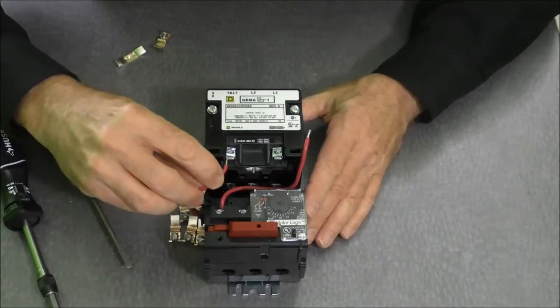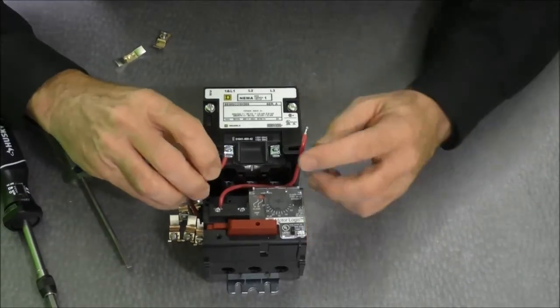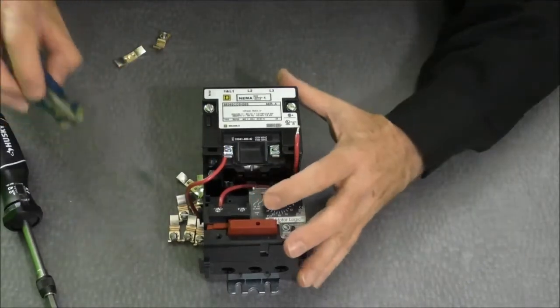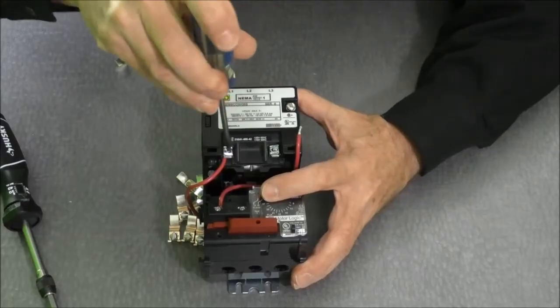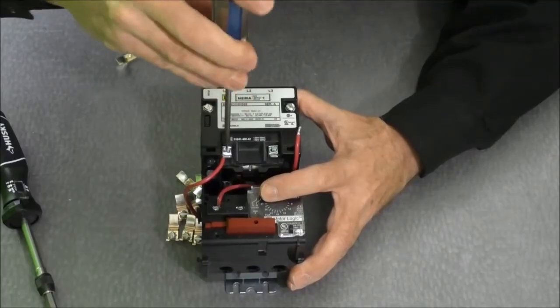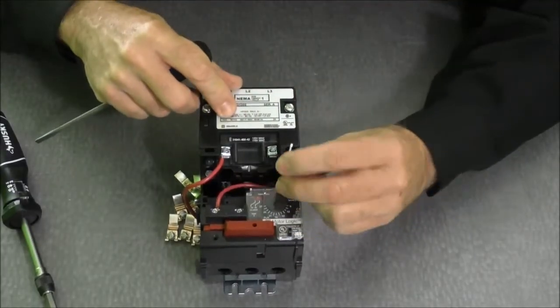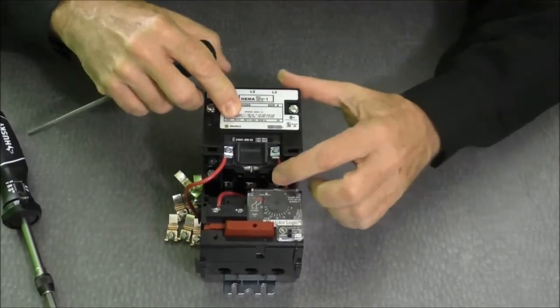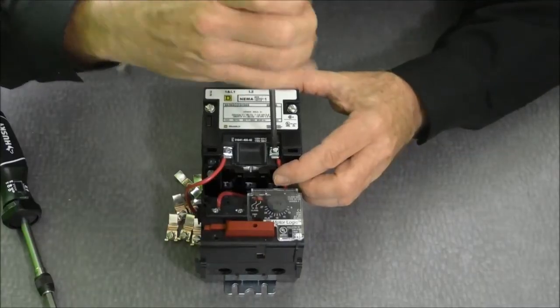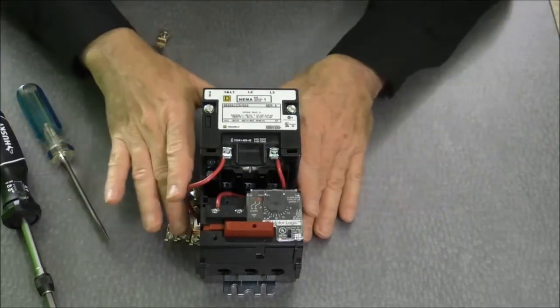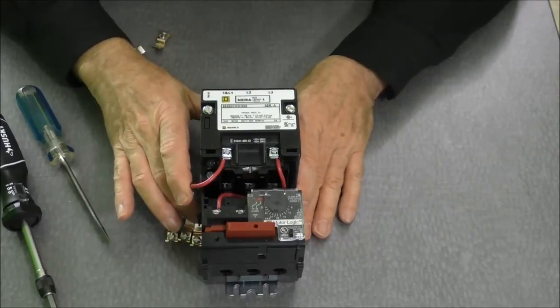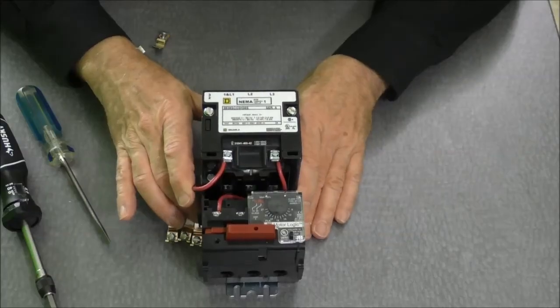The last step is to put the coil wires back onto the A1 and A2 terminals. That's six to nine inch pounds for those terminals as well. So now we have a used starter with brand new contacts in it.